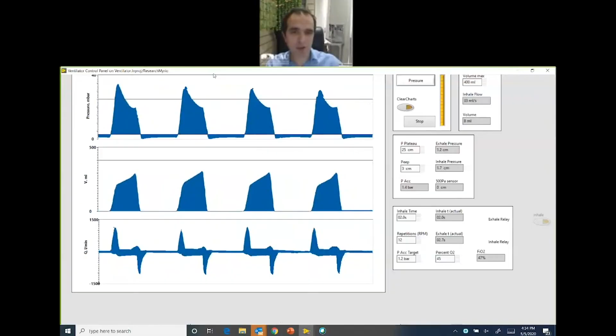The solenoids will just open and close, but unlike some of the ventilators on the market, we do not need to just control the on and off. We also need to control the flow, and this is done using this variable flow valve that we have designed and built. With the variable flow valve, we have a closed loop. We read from the sensor that we have designed the amount of flow being fed into the lungs of the patient, and based on that, we either close or open the valve in a fast way or in a slow way.